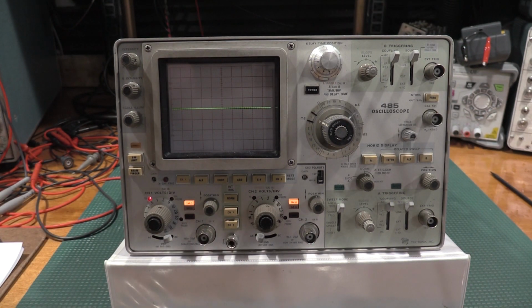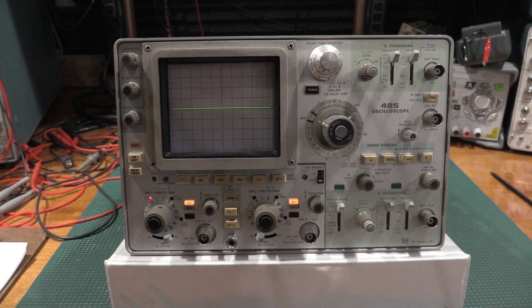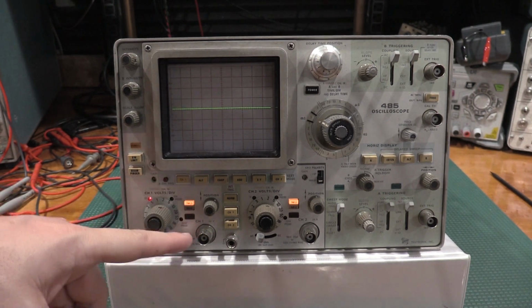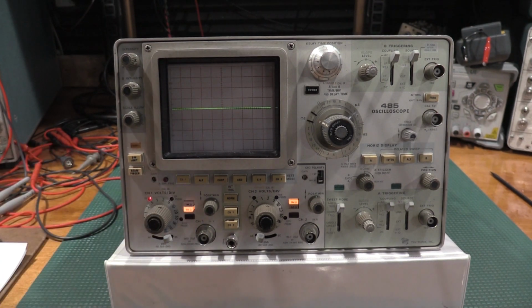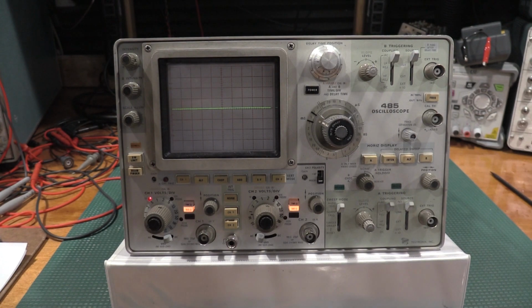For step 44, the calibration document does call for a 106 for a high amplitude square wave generator. The PG 506 non-A will not output enough power to get the 50 ohm load to trip. So it does need to be a 106 or a PG 506A.